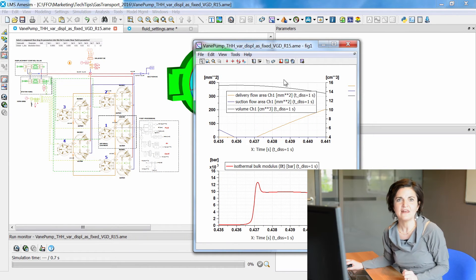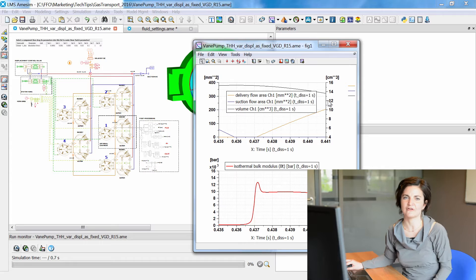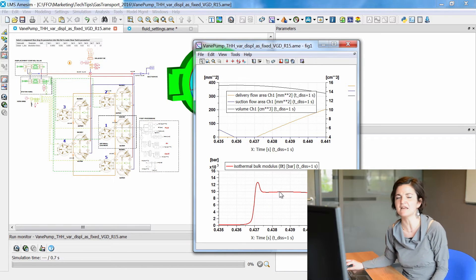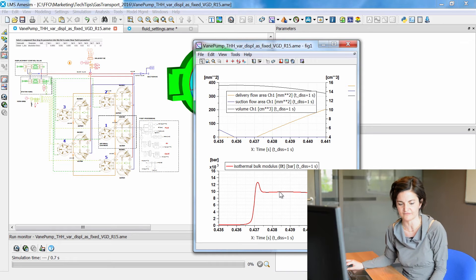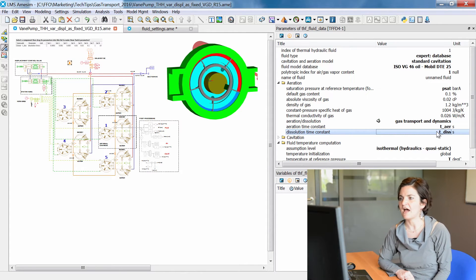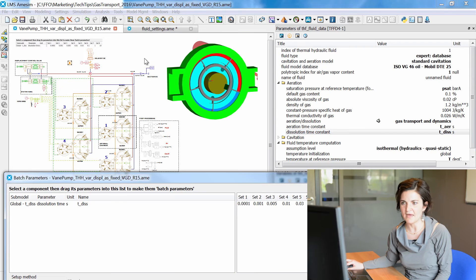The pressure level within internal chambers depends on the volume variation along the revolution of the pump, but also on the port connections to the suction and to the delivery, and finally also on the fluid properties — in particular the bulk modulus, which represents the stiffness of the fluid. Fluid properties and the bulk modulus of the fluid depend on the air amount within the liquid. So we will consider different dissolution times, accessible through the icon on the fluid, and we will run some batch simulations.